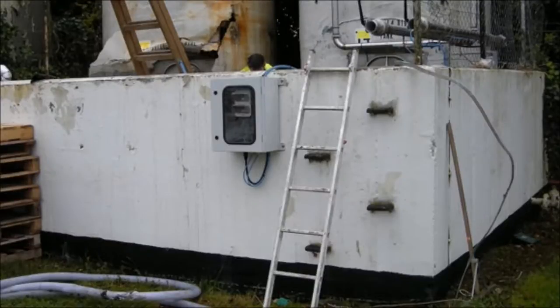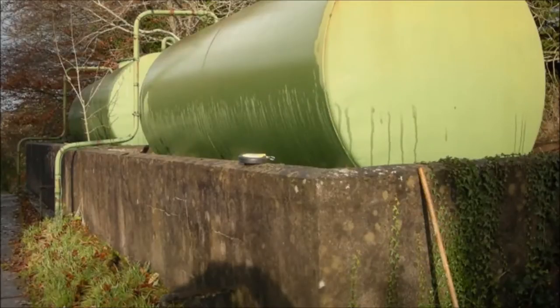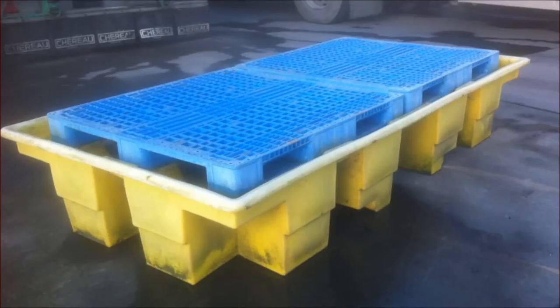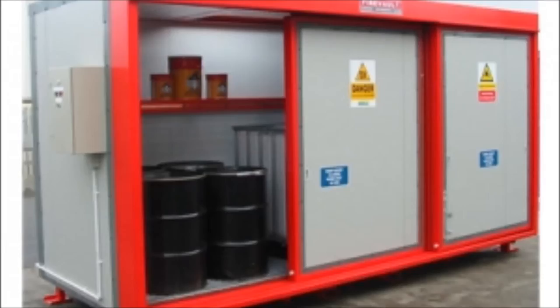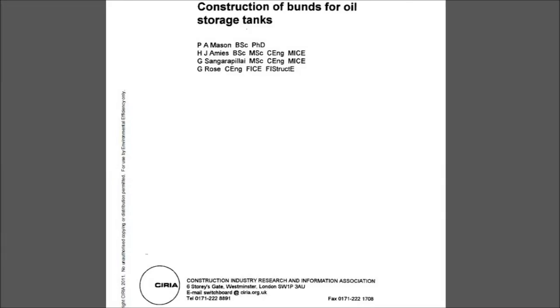The usual material for bund construction is reinforced mass concrete, or sometimes reinforced masonry. Bunds constructed of unreinforced hollow core concrete blocks or breeze blocks are totally unsuitable and have a very high failure rate when tested. An alternative is the sump pallet, manufactured from either plastic or steel, or a bunded storage cabinet, sometimes referred to as a chem store unit.